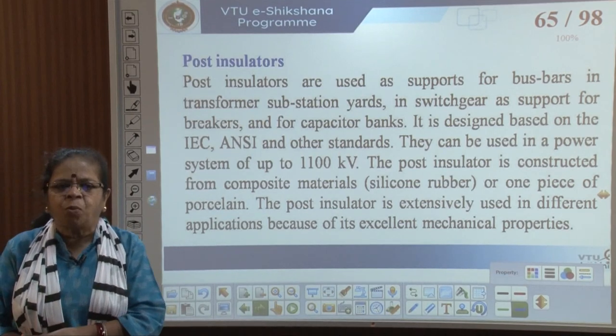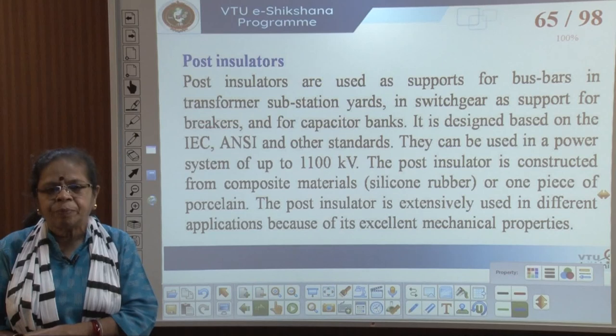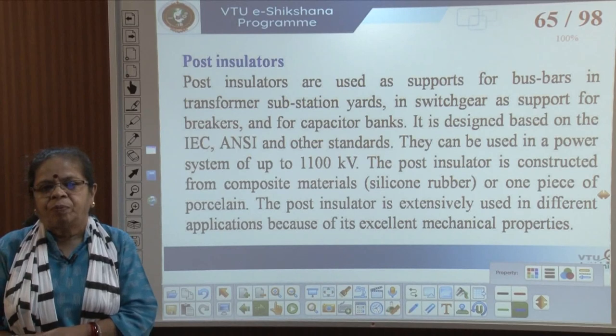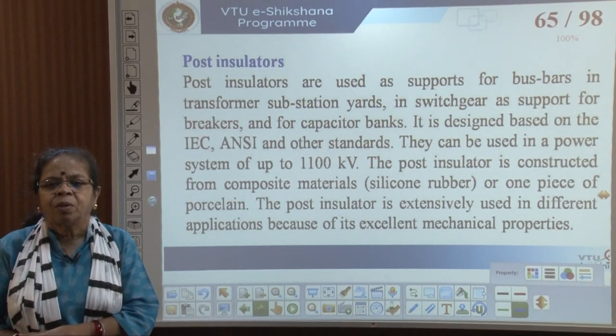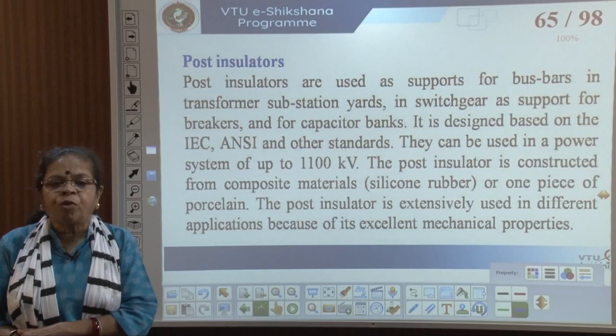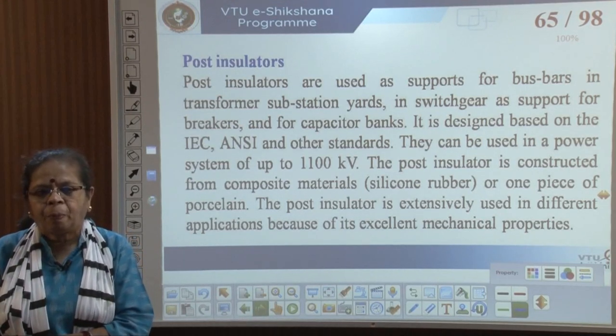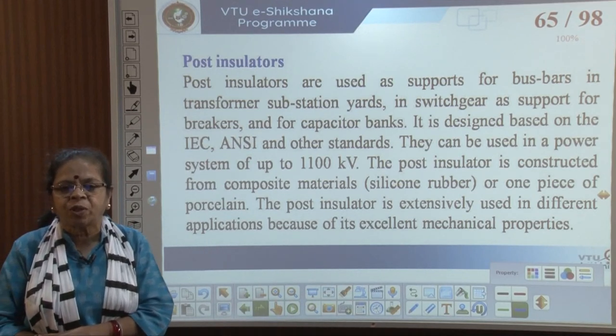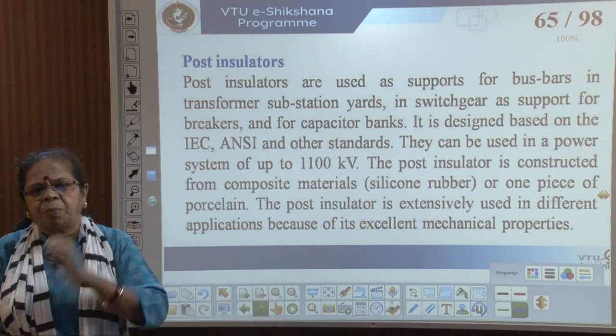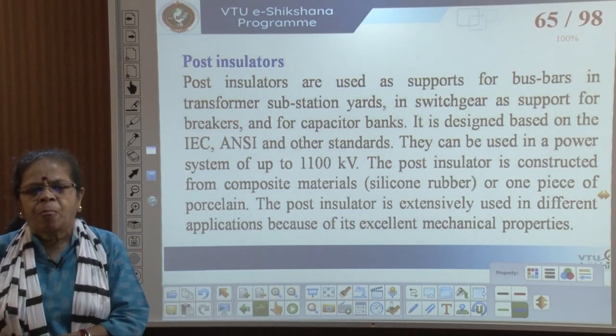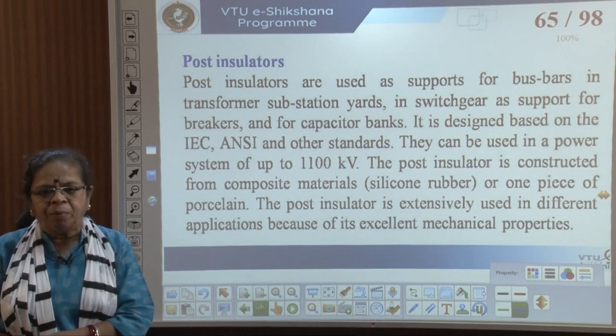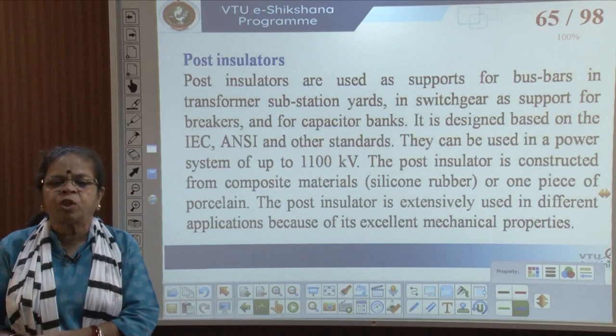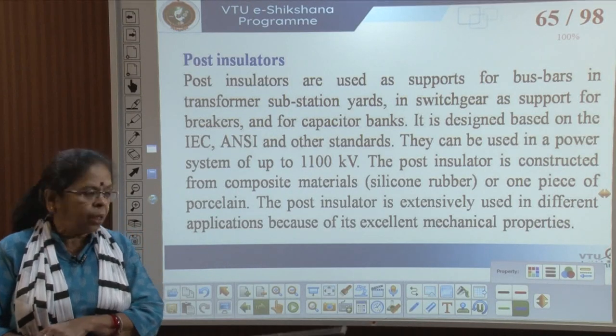There are also more specific insulators. Post insulators act as support for bus bars in transformer substation yards, or as support for circuit breakers and capacitor banks. They conform to IEC and ANSI standards, can be used up to 1100 kV, and are mainly composed of silicone rubber or sometimes porcelain, with excellent mechanical properties.